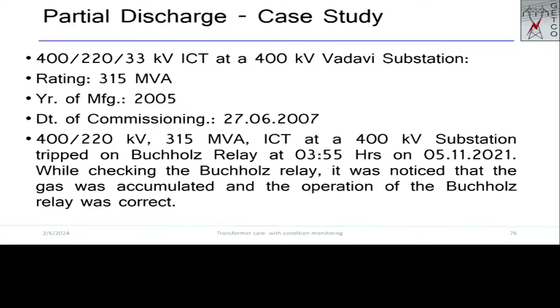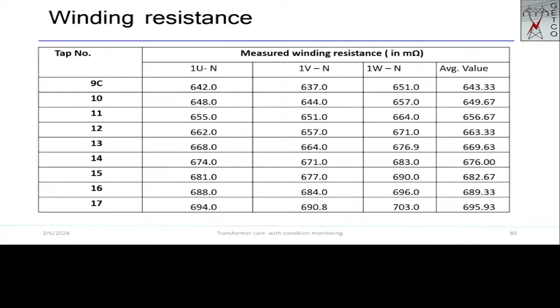So, one of the important case studies of partial discharge: my 400 kV ICT tripped on Buchholz only, okay. So we studied the DR. There was no electrical fault noticed in the disturbance recorder. The transformer tripped only on Buchholz. So DGA test was carried out and acetylene was found in this transformer. So there is something wrong inside the transformer. But each and every test result was found normal. Winding resistance was also found normal. So we were worried and we checked the CFT, core frame earth, maybe that was wrong, but core frame earth was also found normal. So after every result was found normal, we decided to inspect the ICT.